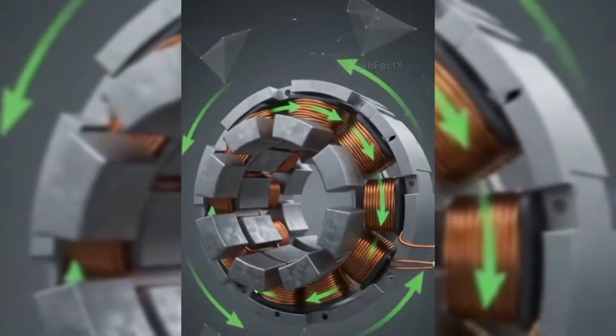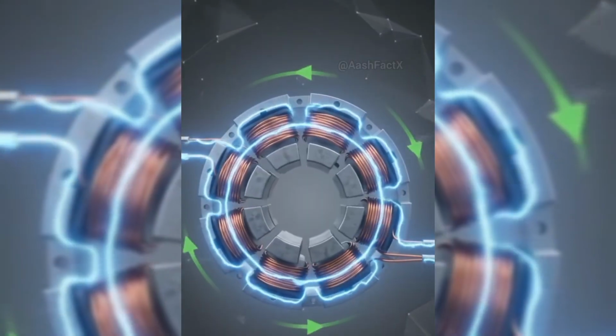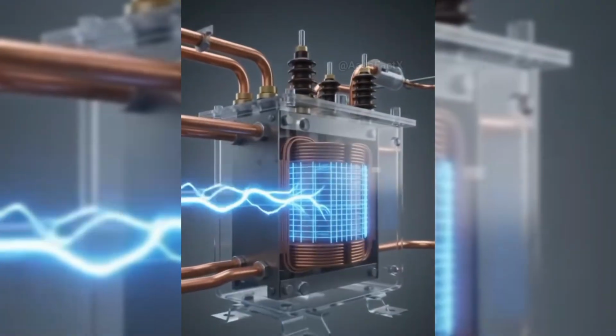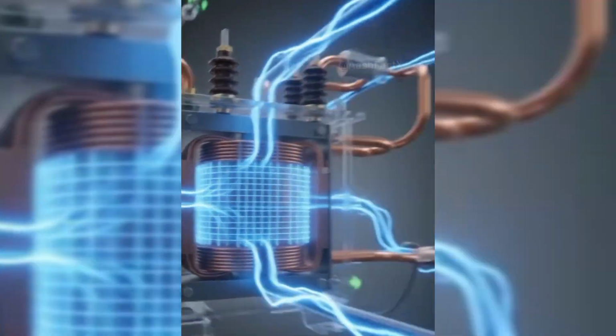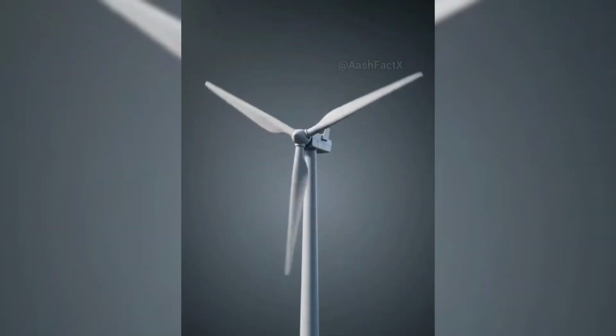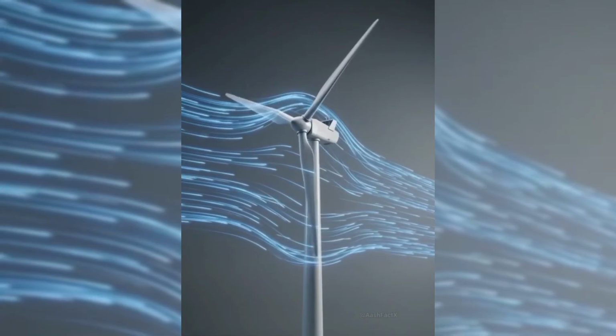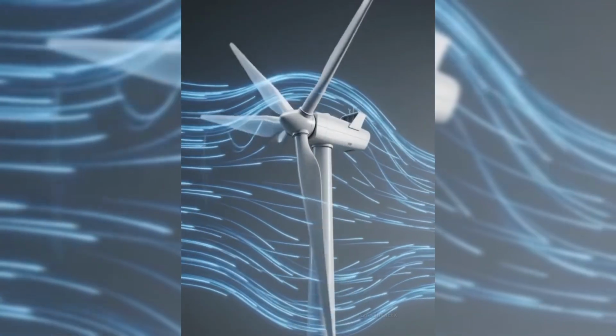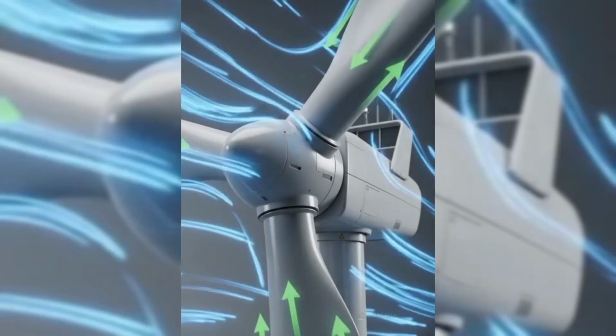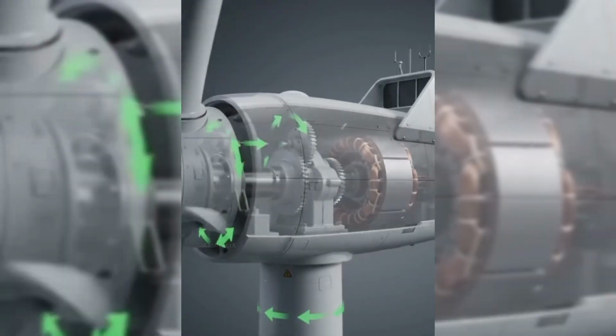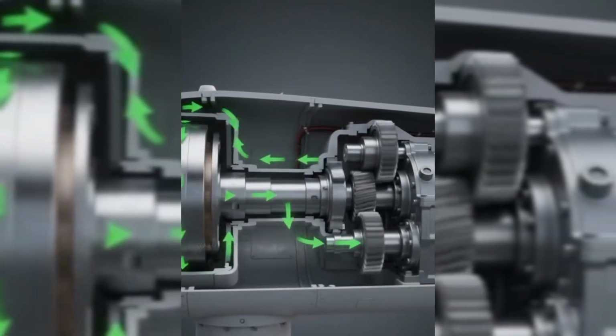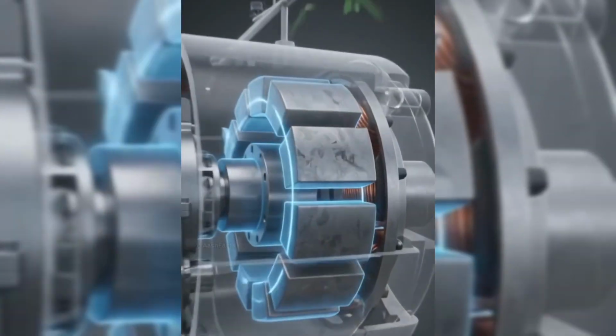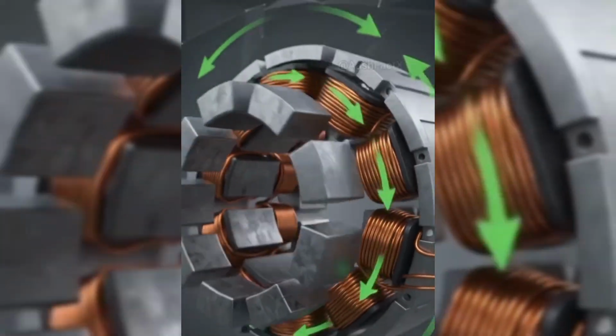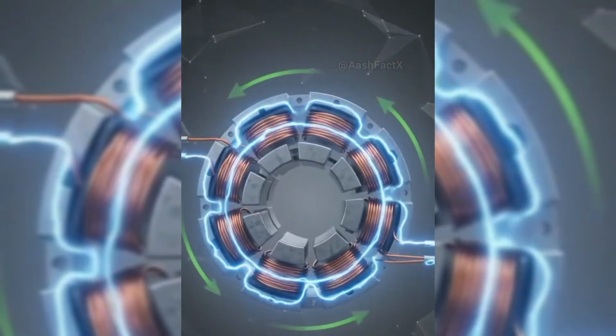Modern three-blade designs are mathematically optimized to balance aerodynamic stability, structural weight, and energy extraction efficiency. As the blades spin, they drive the primary mechanical components housed inside the nacelle, which is the large structure sitting atop the turbine tower. The rotating blades directly turn the low-speed shaft. However, the blades themselves rotate relatively slowly, usually between 8 and 20 revolutions per minute. This speed is far too slow to generate a usable amount of electricity directly.